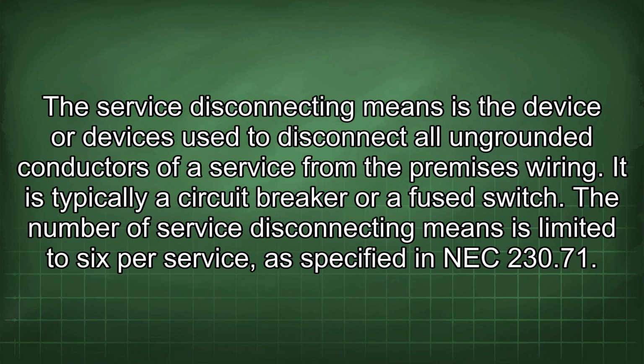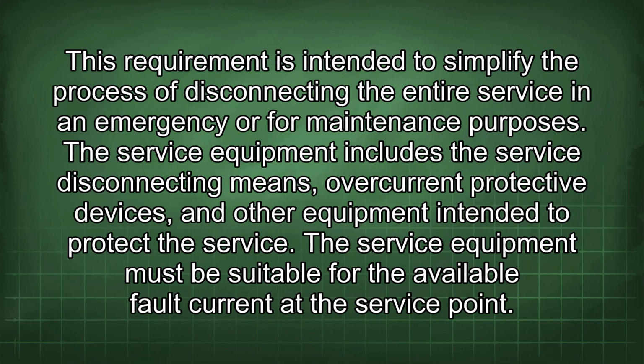The service disconnecting means is the device or devices used to disconnect all ungrounded conductors of a service from the premises wiring. It is typically a circuit breaker or a fused switch. The number of service disconnecting means is limited to 6 per service, as specified in NEC 230.71. This requirement is intended to simplify the process of disconnecting the entire service in an emergency or for maintenance purposes. The service equipment includes the service disconnecting means, overcurrent protective devices, and other equipment intended to protect the service.